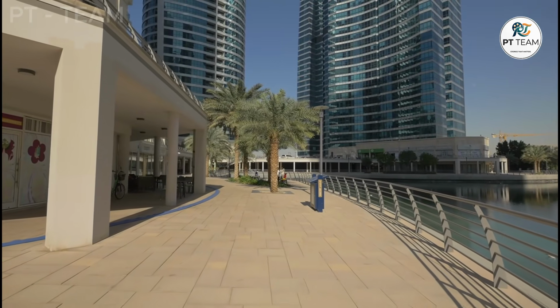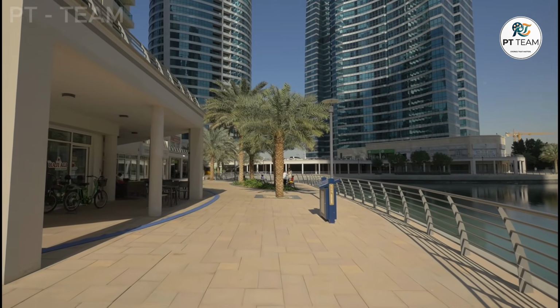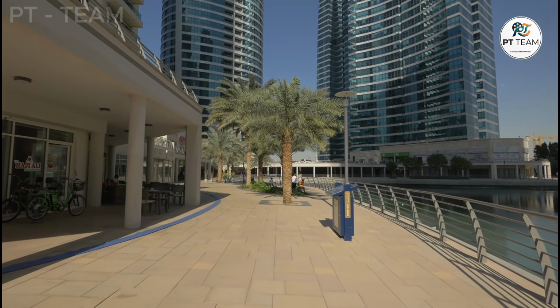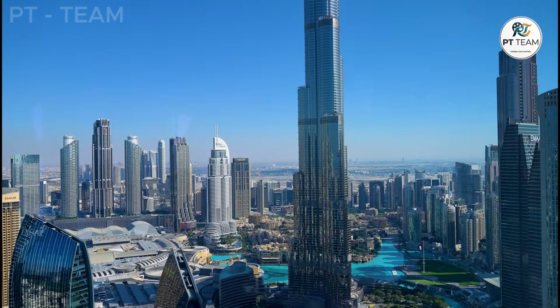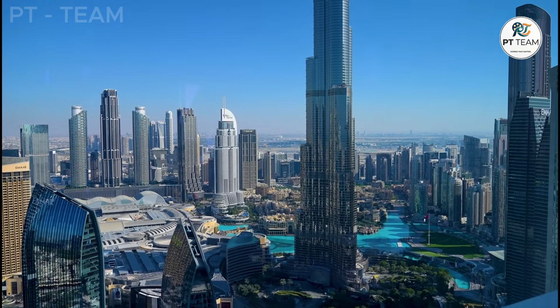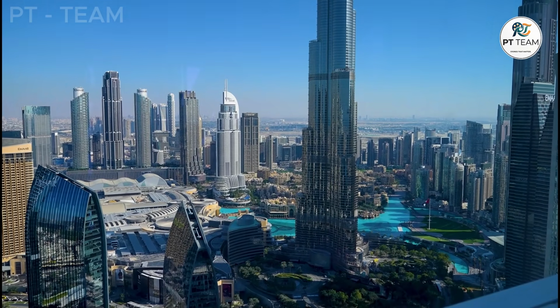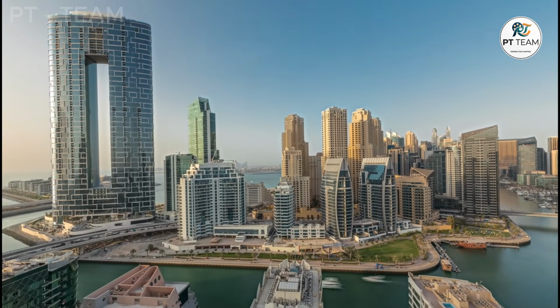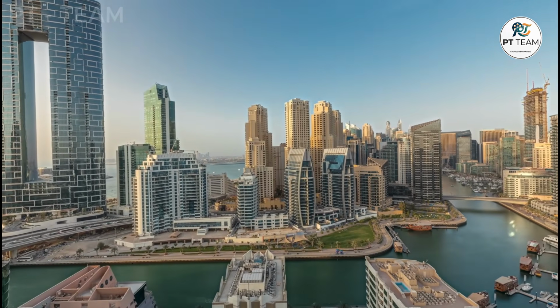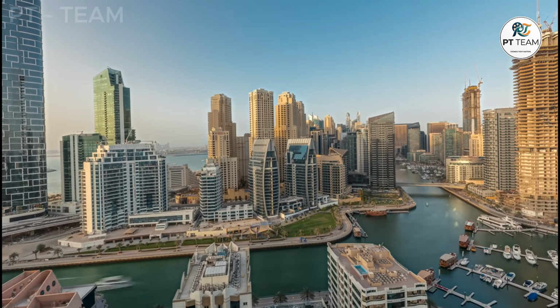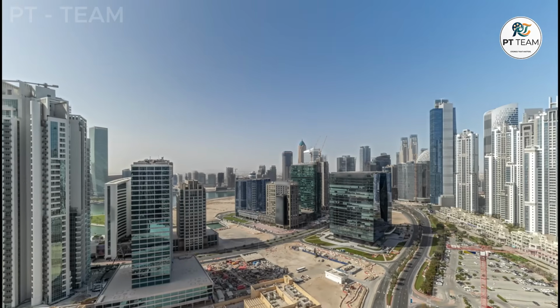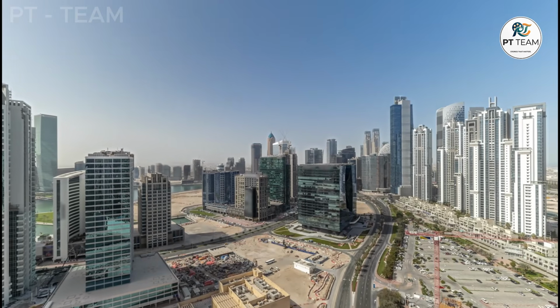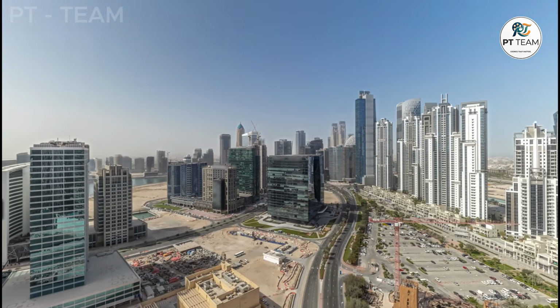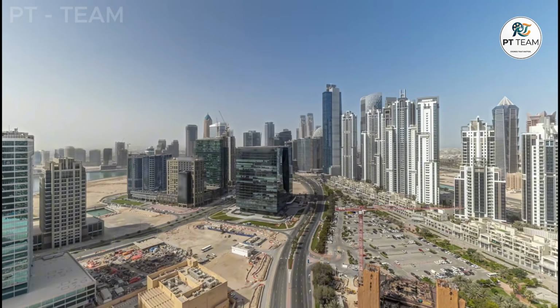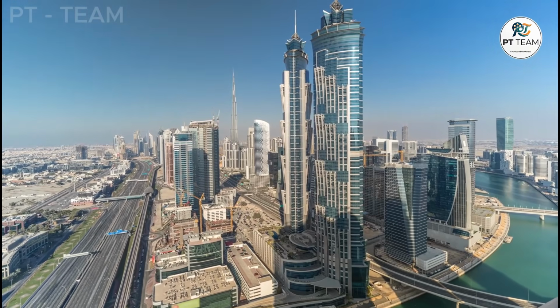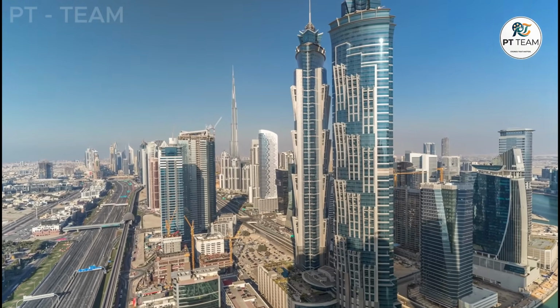Part of the system that carries this heat away begins with a resource Dubai cannot afford to waste. Many large district cooling plants rely on cooling towers that use evaporation to reject absorbed heat into the atmosphere. This process consumes a significant volume of water daily. Using desalinated potable water at this scale would create a massive resource contradiction in an arid environment, burning immense energy to remove salt from seawater only to evaporate that fresh water to cool buildings.